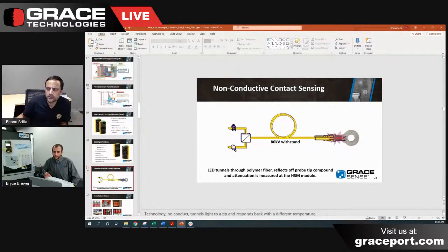Okay, that's good. So we talked about thermography, and there's a limitation. So what is the limitation with this unit? Yeah, the limitation is you only see the local spot. If you're doing a bus bar application, heat will travel some down the bus bar, but it can be difficult to determine. So if I'm trying to pick up a remote location, that's really not the ideal thing, because trying to determine what is an alarm level there can be difficult. So that's one limitation. We do have 18-point and 9-point units.